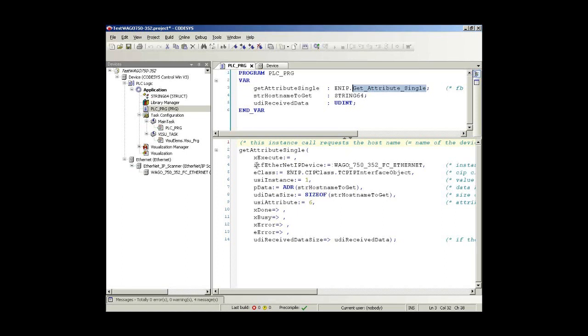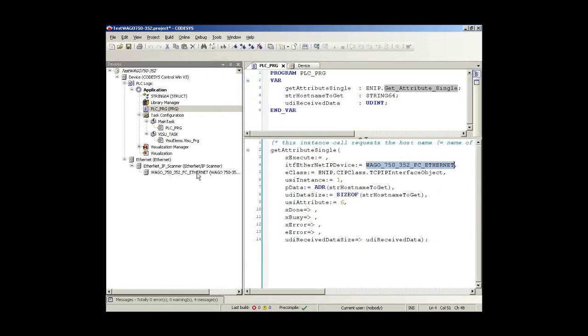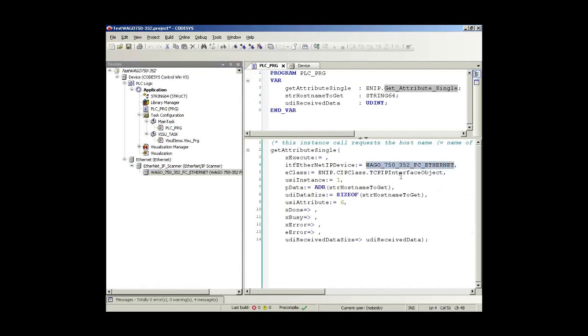There is a certain configuration. One important thing is that you have to enter the interface. And the interface is exactly the name that you have chosen for that EtherNet/IP adapter. So in case you change that name here, you should change as well the name in the call. Then we overgive some parameters, for example the CIP class, the user interface, some addresses and space for the data.